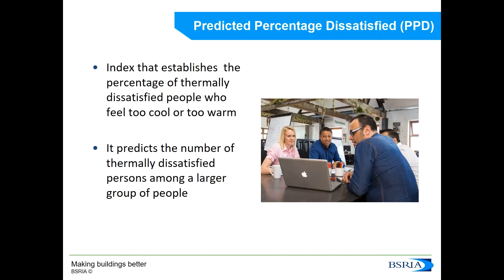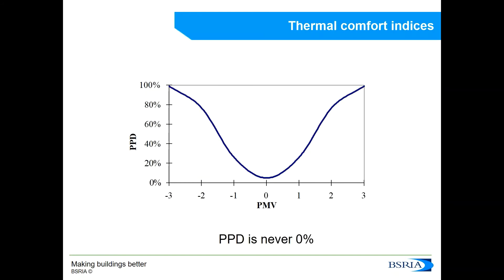The next index is the PPD or Predicted Percentage of Dissatisfied. As its name indicates, the PPD predicts the number of people who are going to feel uncomfortable in a certain environment. As we can see in this graph, PMV and PPD are related. If people voted that they were feeling extremely hot or very cold, then 100% of people would feel dissatisfied. As the PMV approaches zero, the PPD goes down. But PPD is never zero percent because there will always be a percentage of people who feel dissatisfied with the environment.